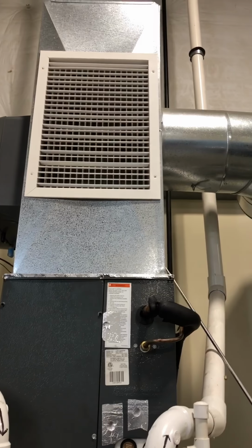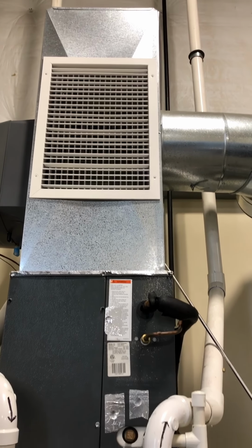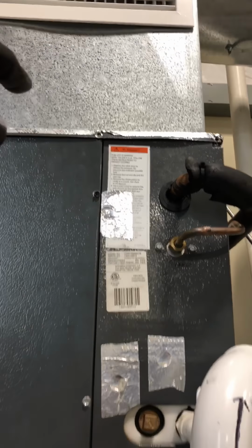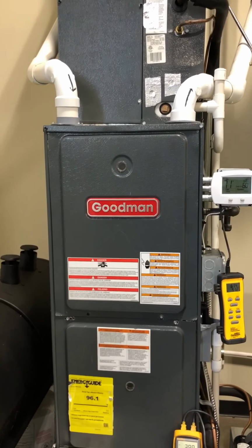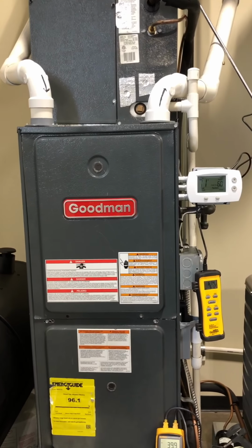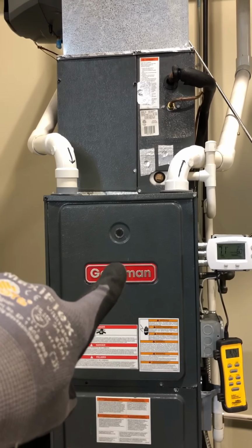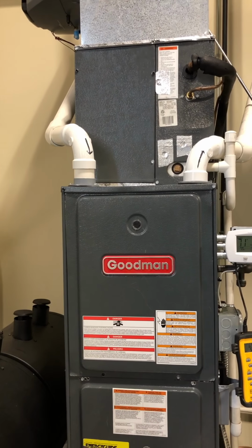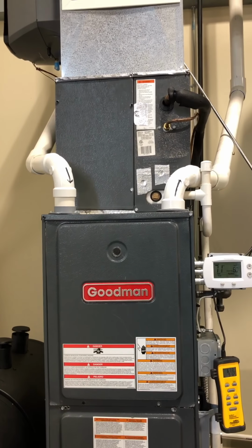Next, I'm going to check the temperature split inside the house. Again, this is a training environment, so I just got this big vent here, but you go up to a vent. You can do it right across the furnace, or right across the evaporator. You can do it that way. I don't like to do it that way because in a real life situation, I like to take my temperatures at the vents. I'll take them at the furnace too, to make sure I got a good temperature split there. But then I like to go into the house and make sure I got roughly the same temperature coming out, maybe a couple degrees more, because we'll lose some in the ductwork. But I don't want to be losing a ton in the ductwork.